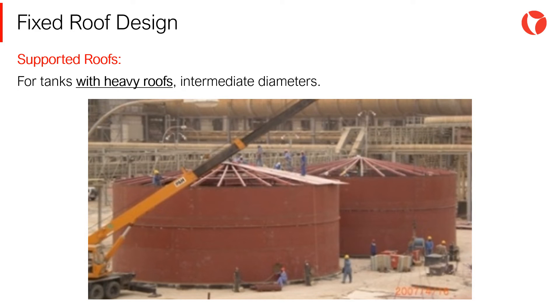Supported roofs share the same characteristics as the self-supporting type, although in this case a structure is used to support the roof plates. The main reason for using a frame is due to the weight of the plates to be supported and the external loads applied to the roof — such as weight, mechanical elements, snow, etc. Depending on the diameter of the tank and the loads to be supported, the roof will be designed with or without columns.